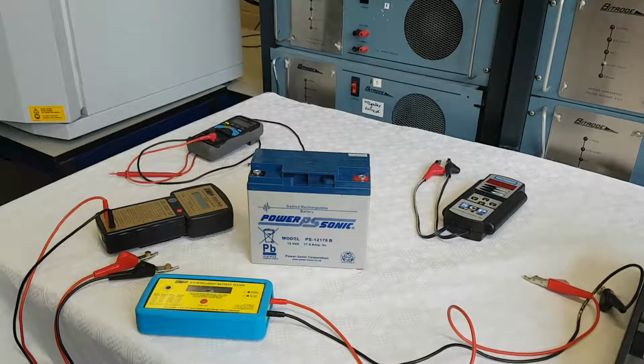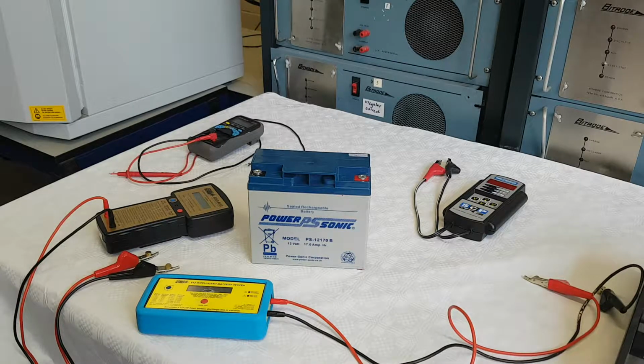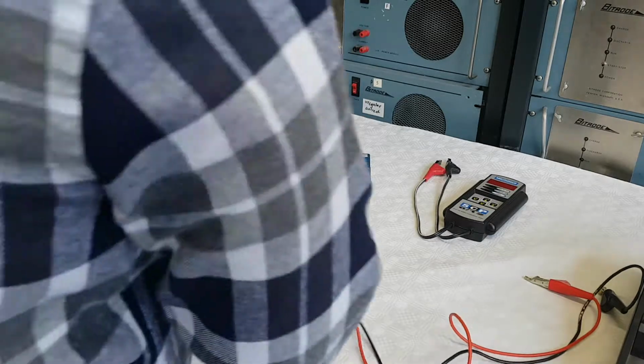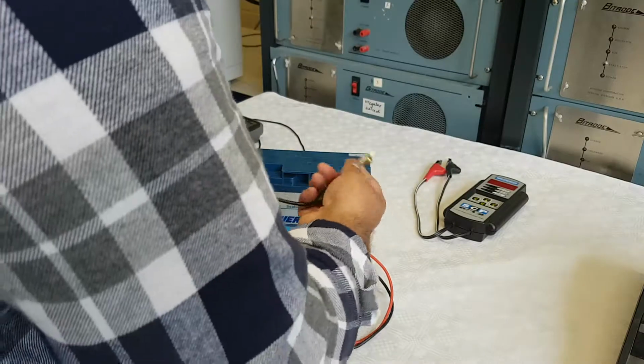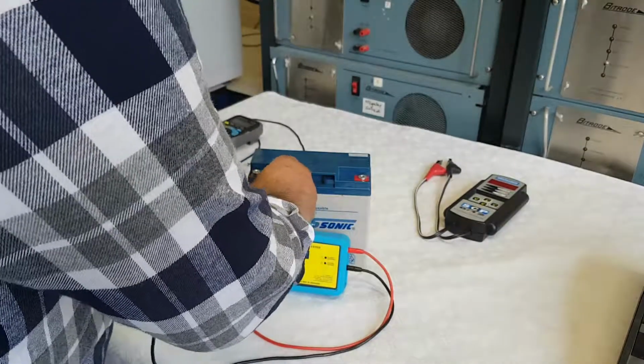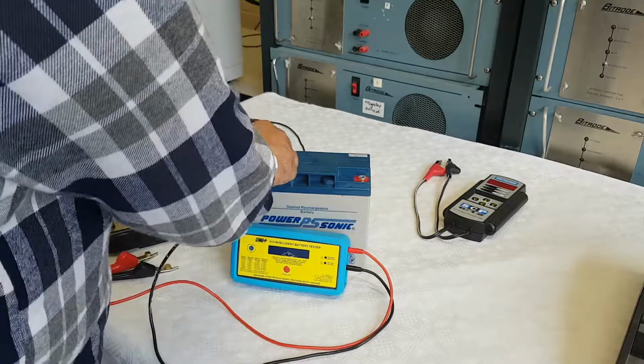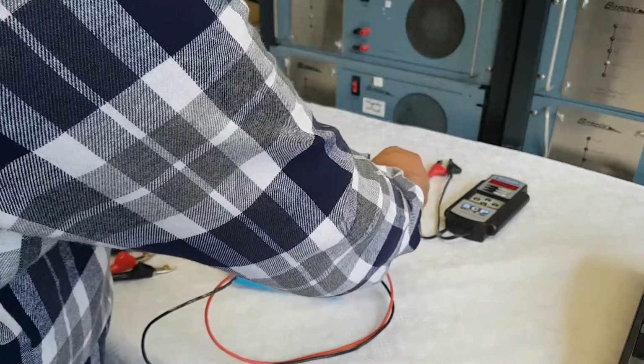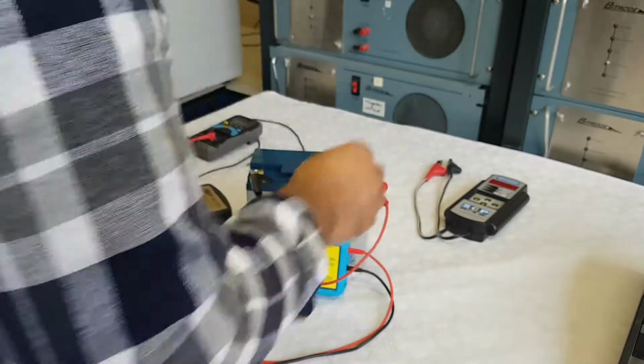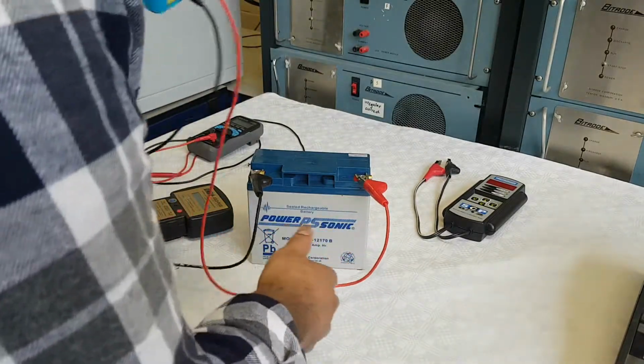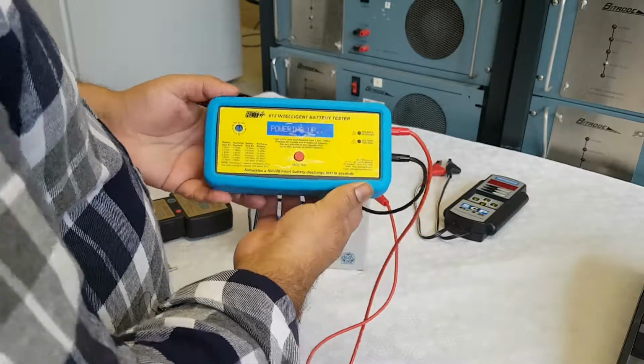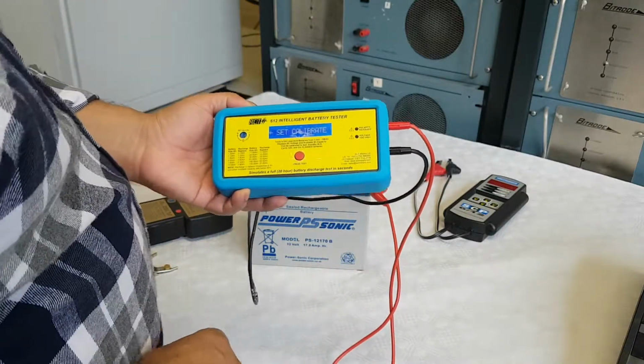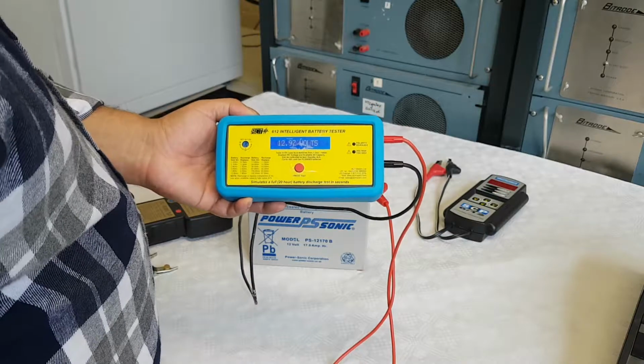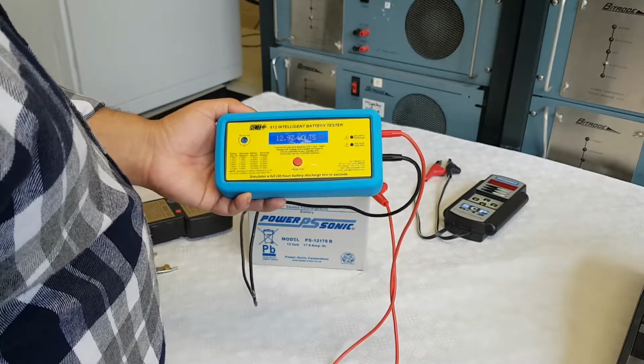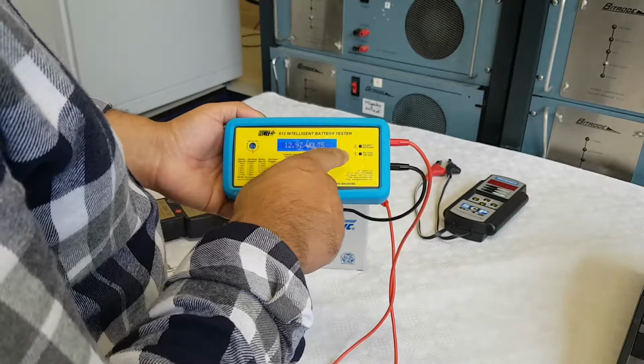Okay, next we're going to do a battery test using the latest ACT battery tester. Again, making sure we get good connections on the battery terminals. Okay, it's powering up at the moment. Set to calibration, down at 0. That's the on-load voltage. Press to start.